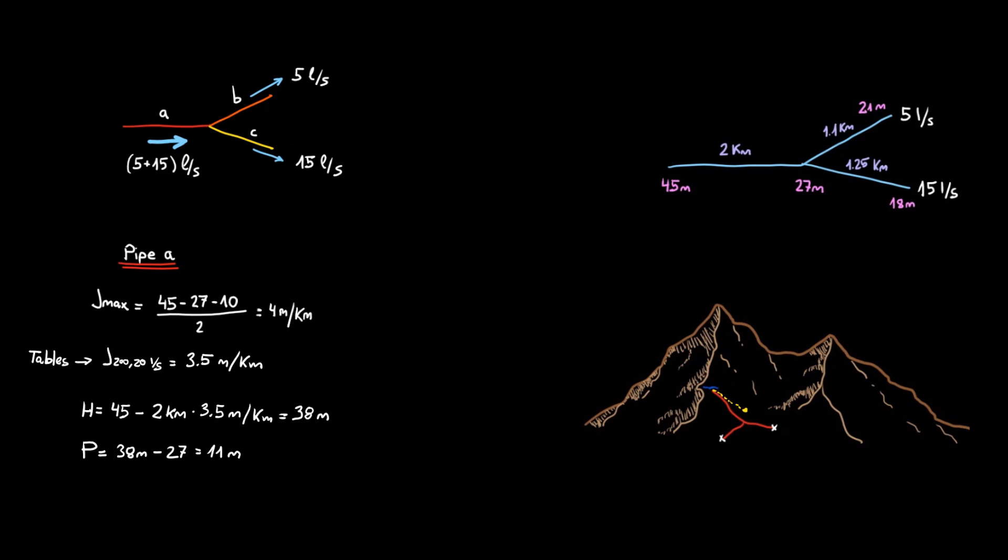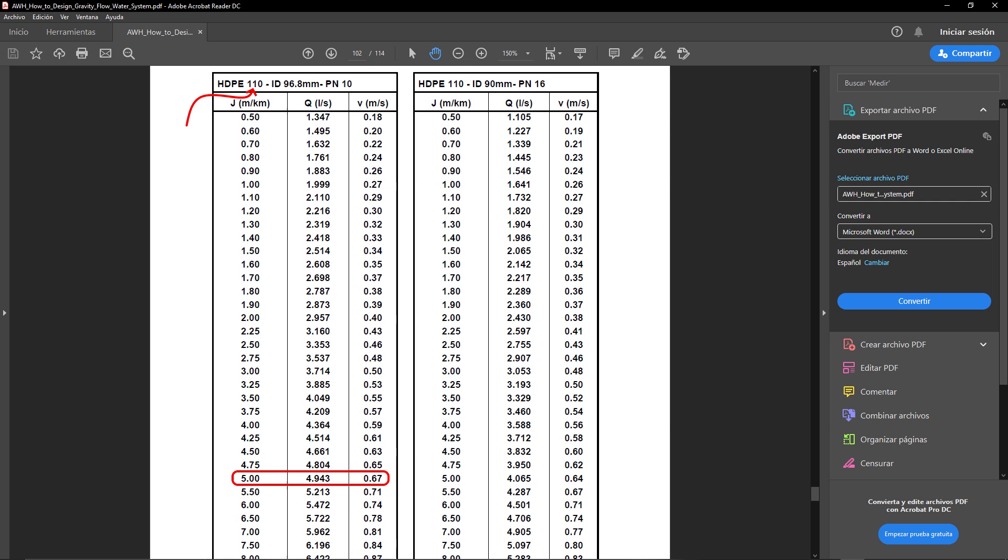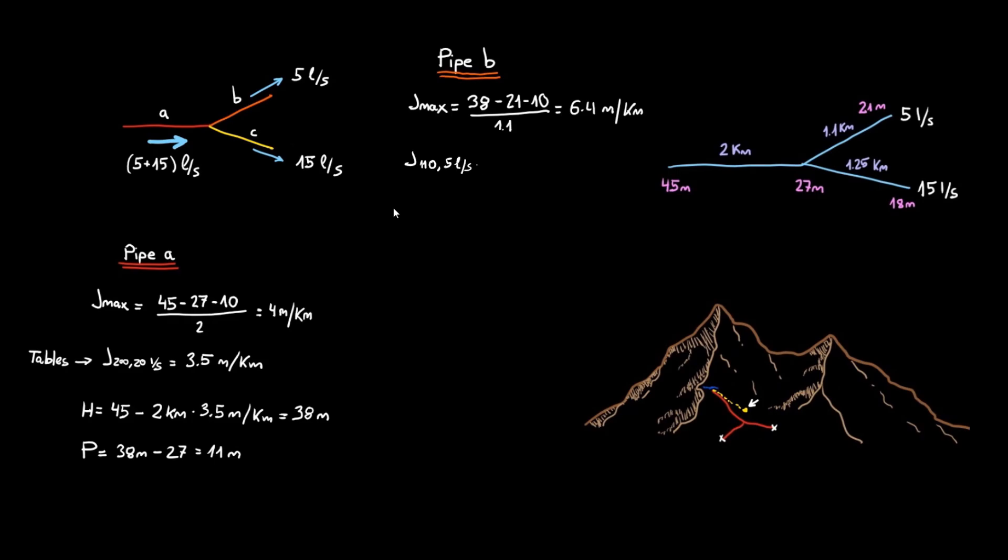We repeat this process for the other two pipes. The starting point is now 38 meters, the head we calculated at the fork. We need head loss values below 6.4 meters per kilometer. This time, the flow to enter in the charts is 5 liters per second. A 110 millimeter pipe gives 5 meters per kilometer. The head at the end point is the head at the start minus the losses. The pressure is above 10 meters, which is enough for ground level use.